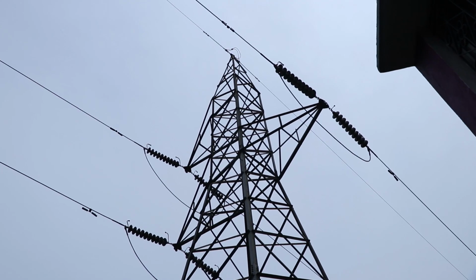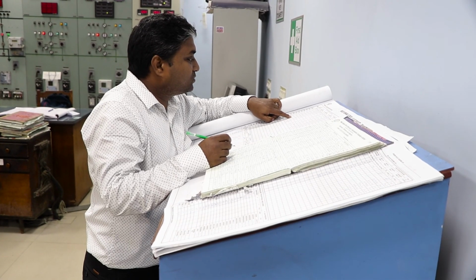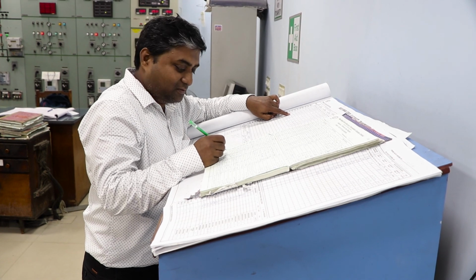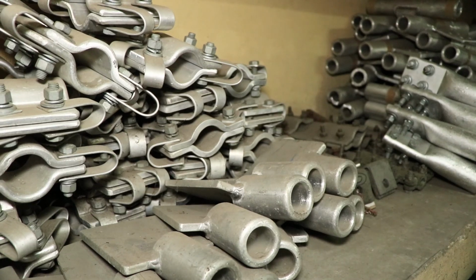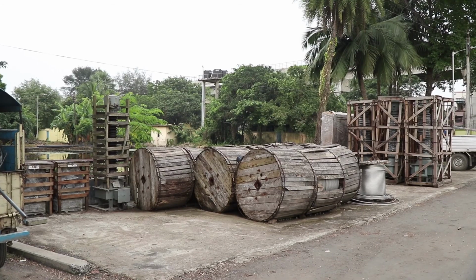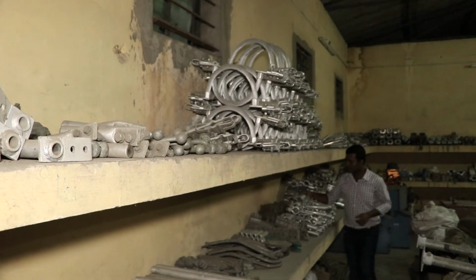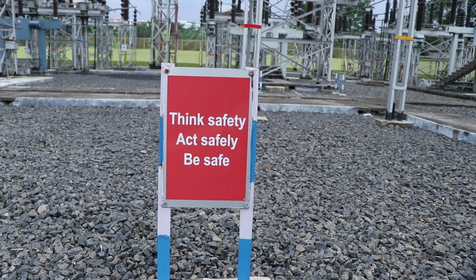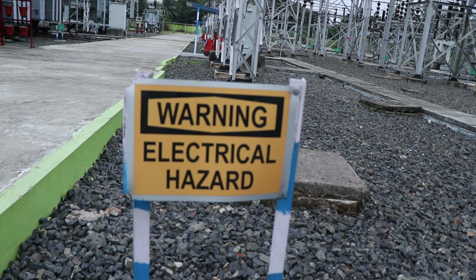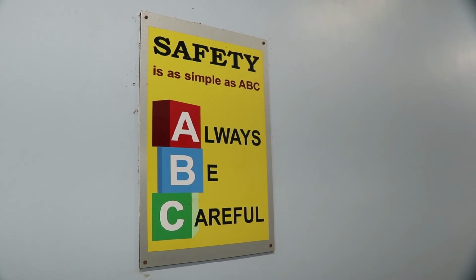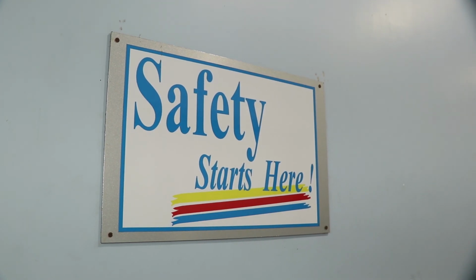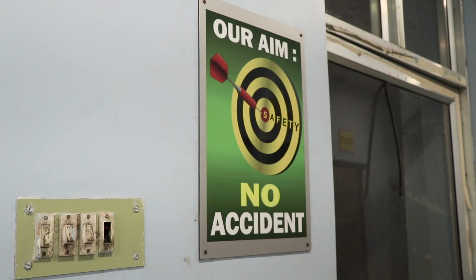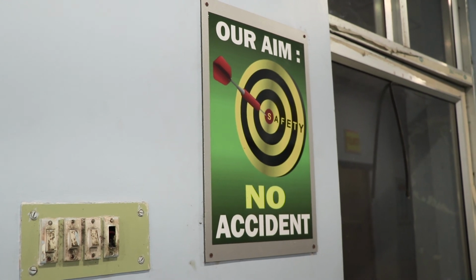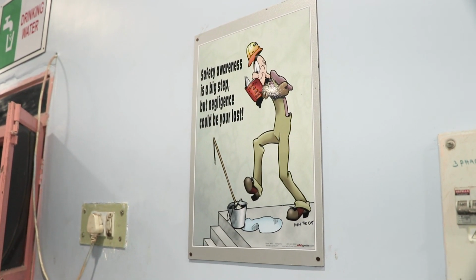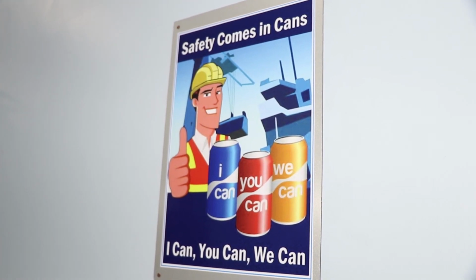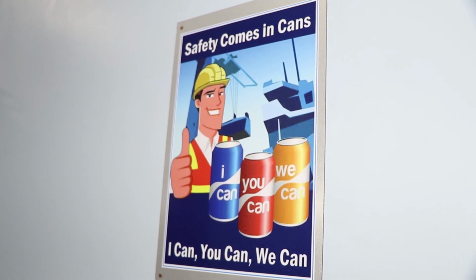Every work and incident is recorded minutely in system book, log sheet, tripping register, etc. We have a well-maintained store where equipment, clamps, connectors, cables, conductors are kept in proper order. Safety is the topmost priority in our substation. During works, safety norms and regulations are minutely maintained to avoid any unprecedented incident. Safety briefing and demo presentation is done for working personnel before actual work. Safety logos, banners, bay marking, phase marking are placed in working areas for awareness of the working personnel.